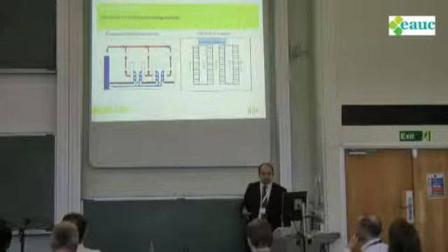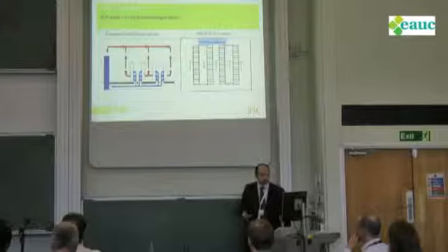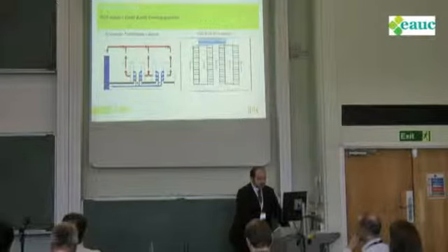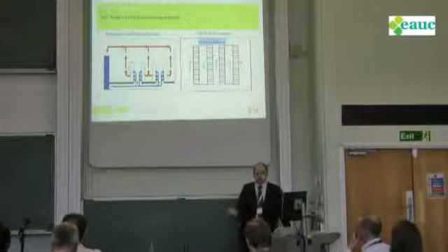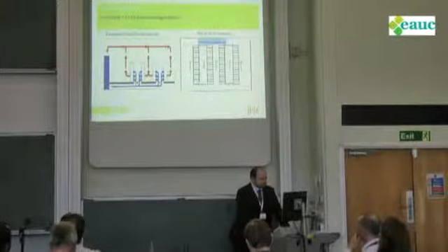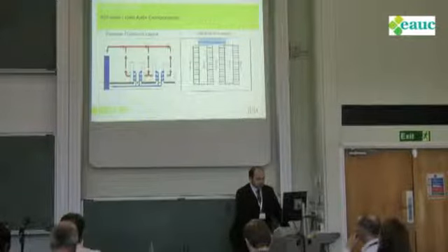It's actually not particularly effective because you've got ample chance for air to mix in this space. Hot air moves like a liquid and will go all over the place if you allow it. So what you can do is, in this example, you've got your cold and hot aisles, looking from above.